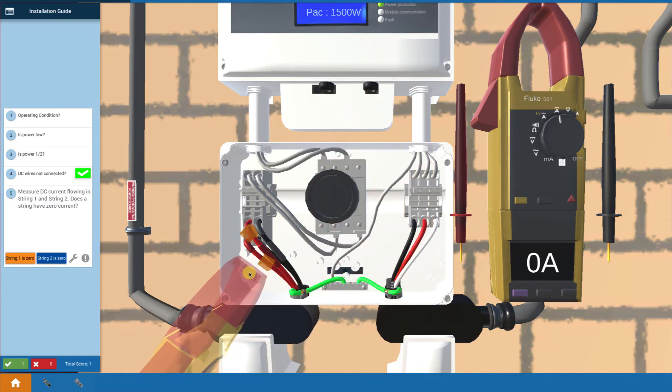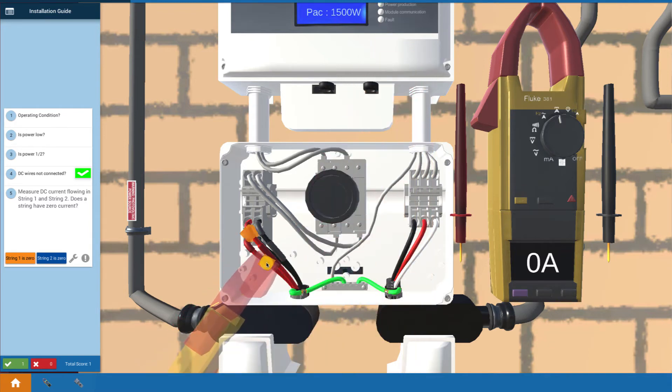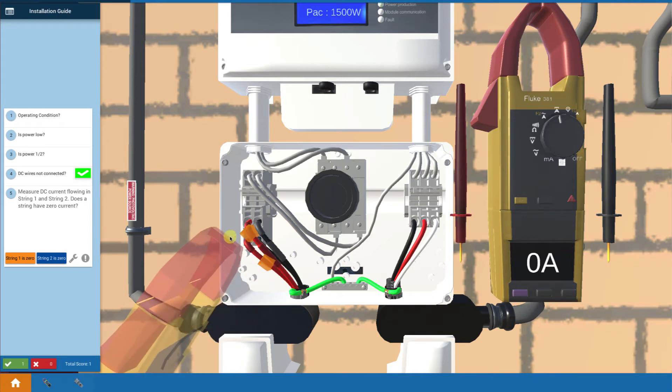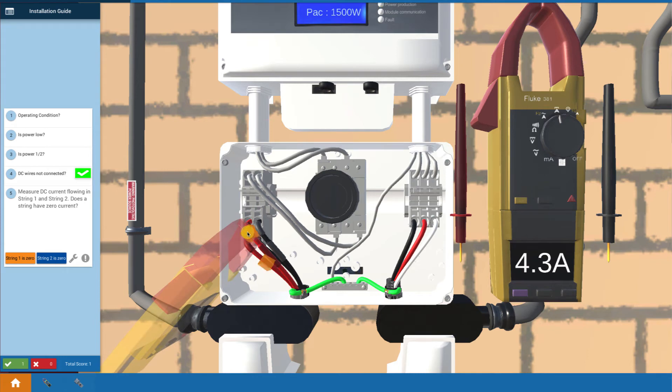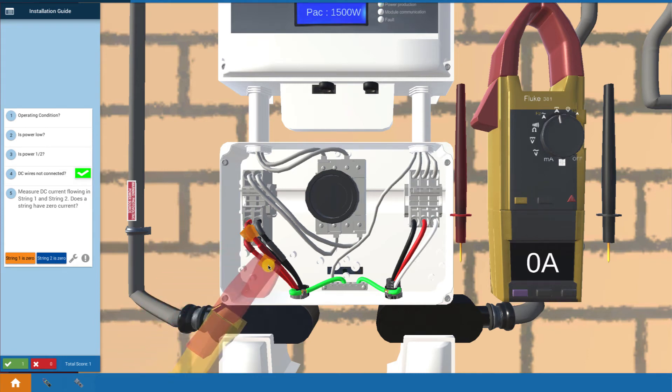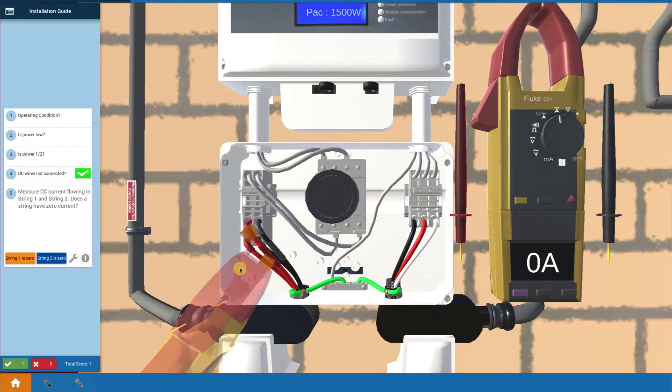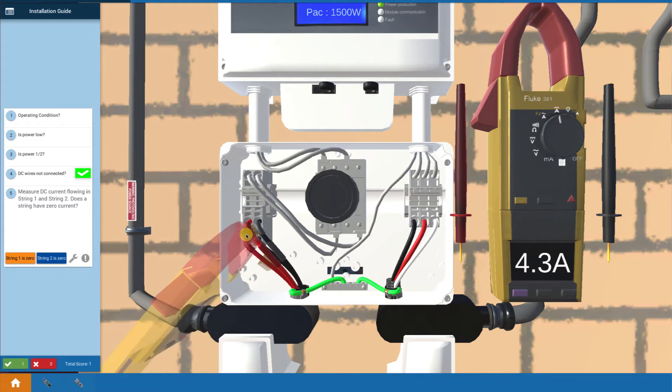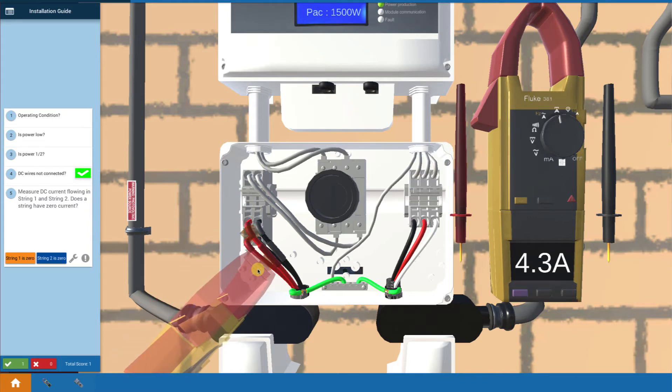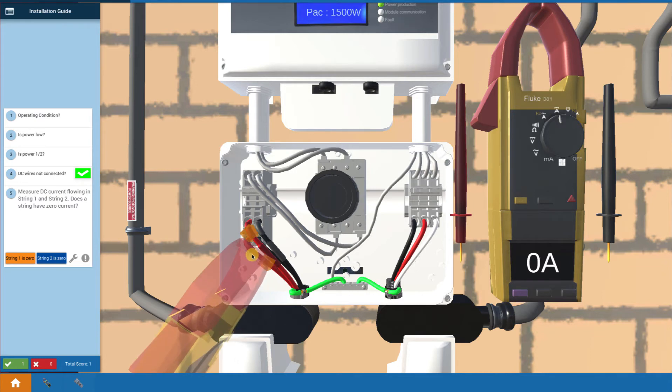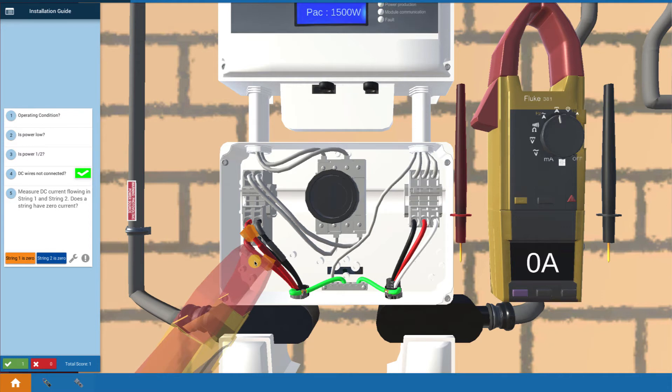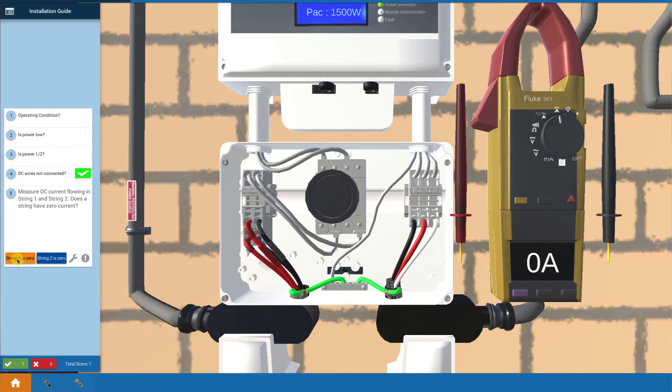I'm going to touch my probe here for string one red wire. I get zero amps. I'm going to click over here, I get 4.3 amps for string two. Come back and check again. String one, I'm getting zero if I clamp around it, but number two, I'm getting 4.3. That tells me that my current flow in string one is zero. I've got a problem with string one. Now I can start examining those wires.